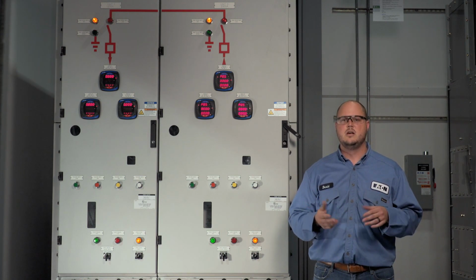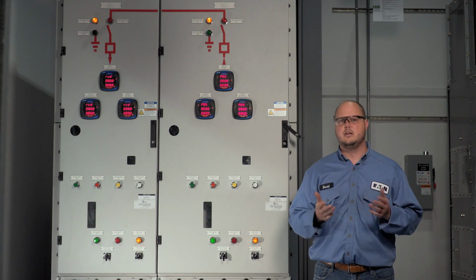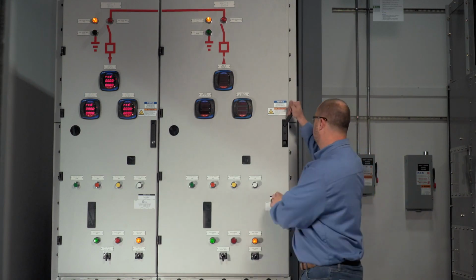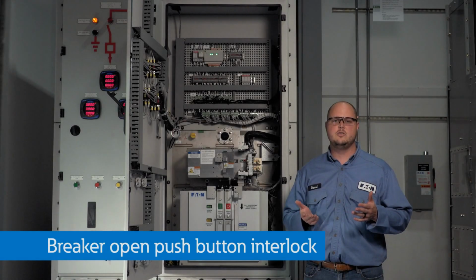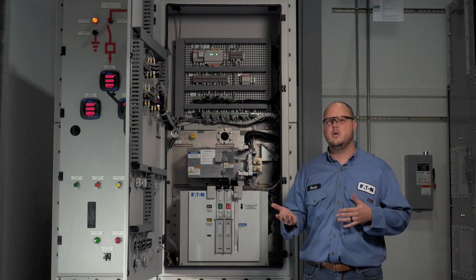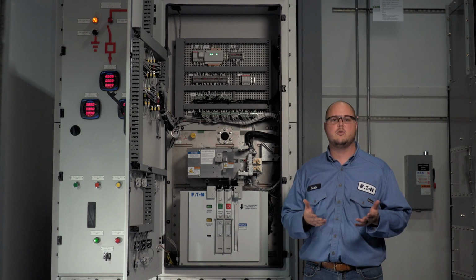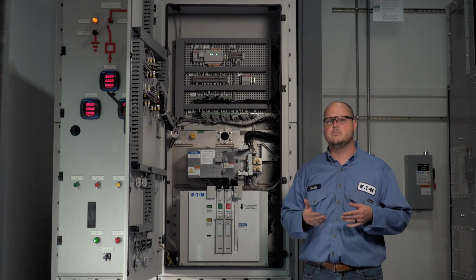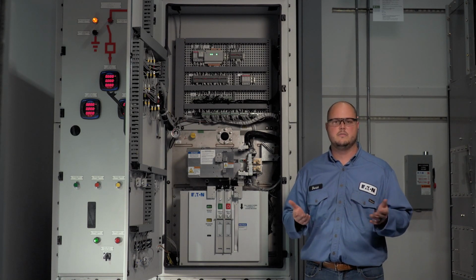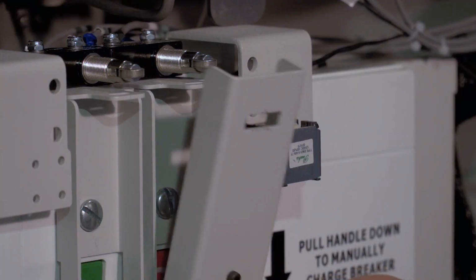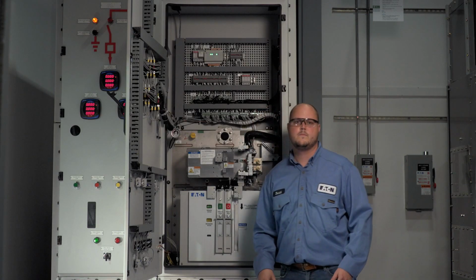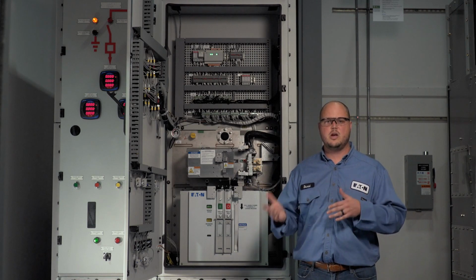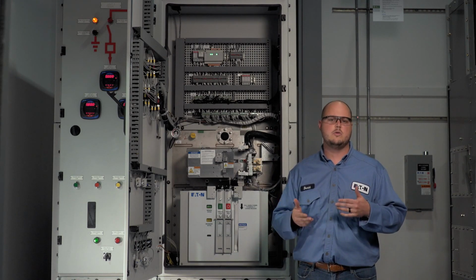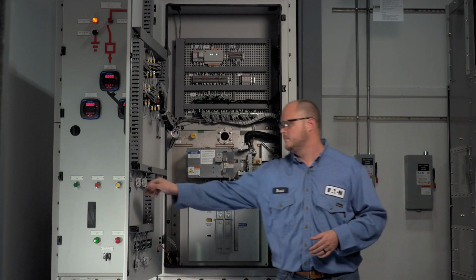Before grounding the switch, let's look at the breaker open push button interlock. The breaker open push button interlock is used to prevent tripping of the breaker only when the 3-position switch is grounded. Note that while the switch is ungrounded, the interlock coil prevents the operator from applying the breaker open push button interlock cover. So let us move the switch to the ground position and visually verify that the 3-position switch has been grounded.